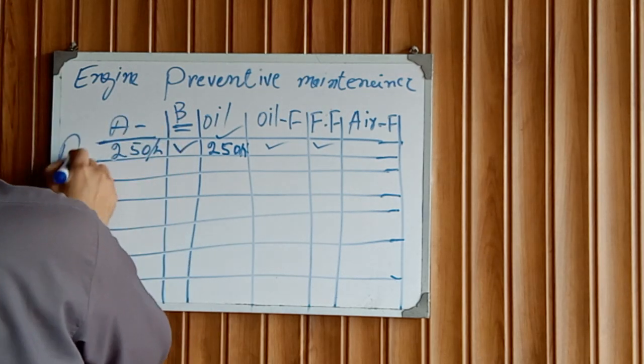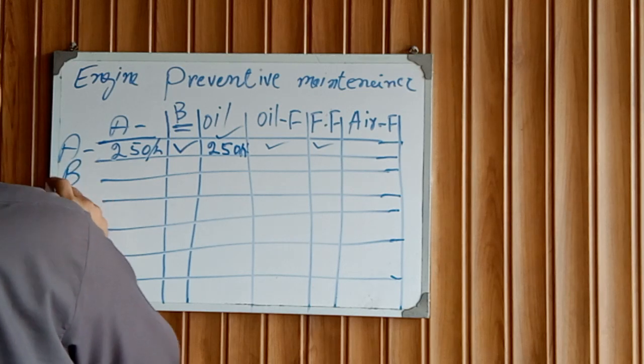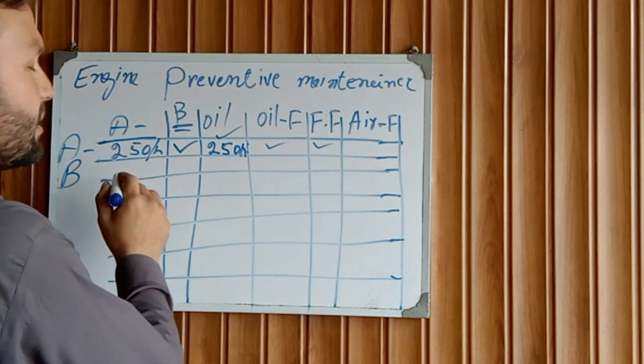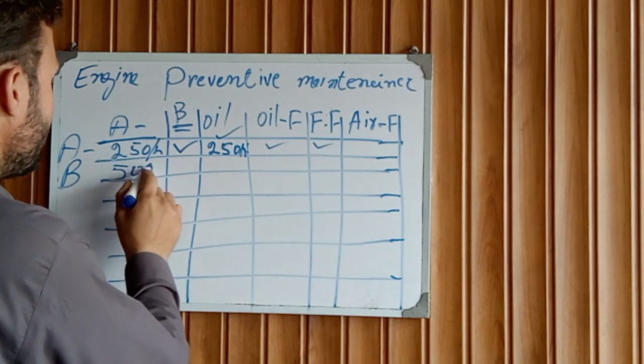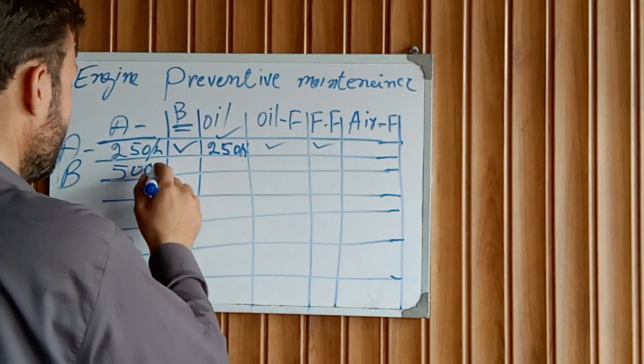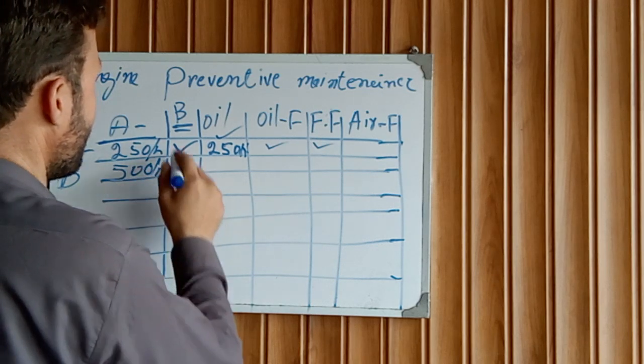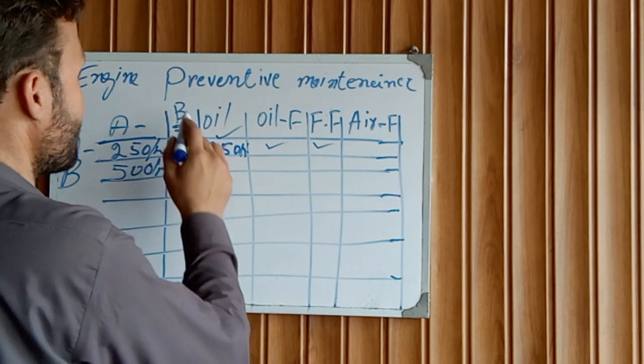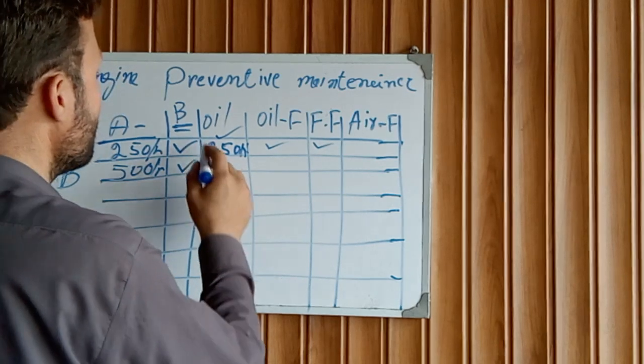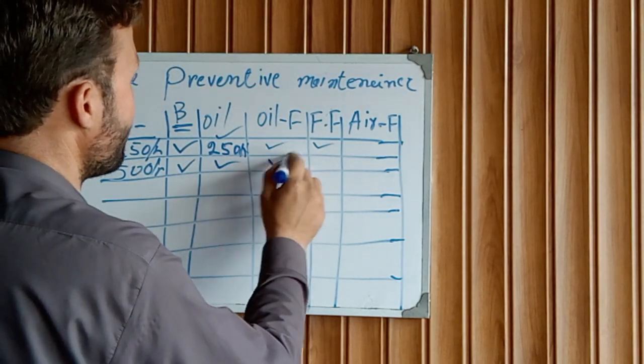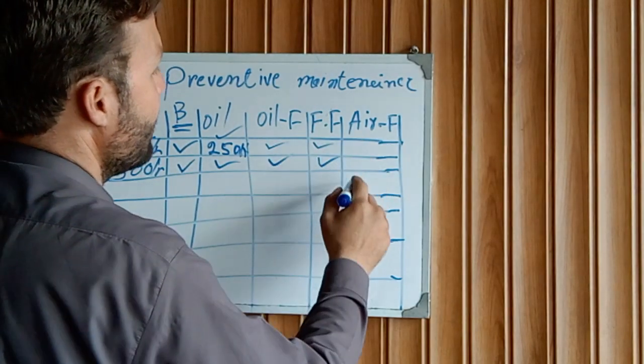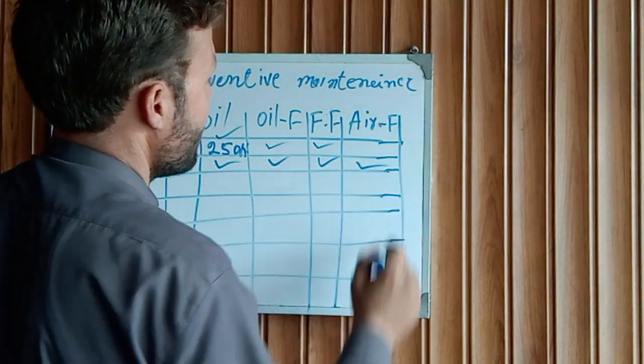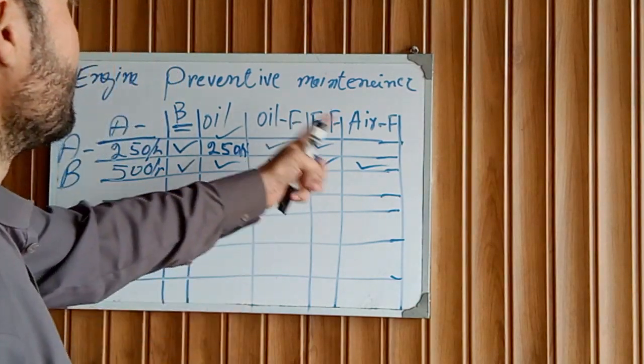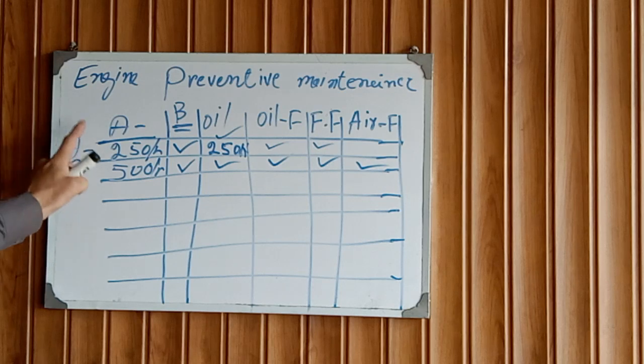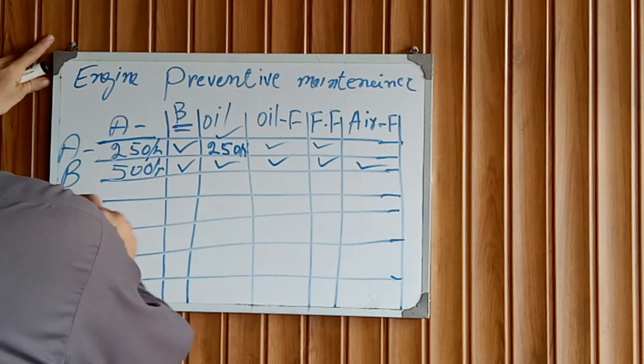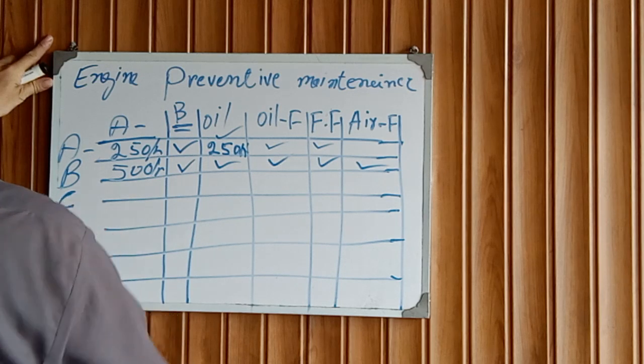This is the A maintenance, this is the B. After 500 hours completed, after your generator runs, you need to check the battery, distilled water, and clean the battery posts. Also change the oil, oil filter, and fuel filter, and also change the air filter. This is the B maintenance. Now moving to the third one, this is the C.